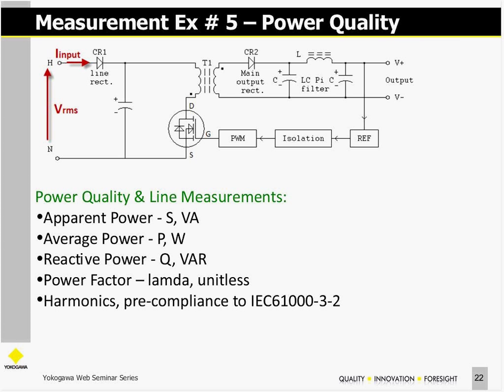Okay, power quality. When I say power quality, I'm generally referring to harmonics. Each of our scopes with the power analysis package is capable of performing pre-compliance tests to IEC 61000, in particular 3-2, which is the current measurement, the harmonic current. At the same time, we'll talk about apparent power, symbol S, with units of volt amps.